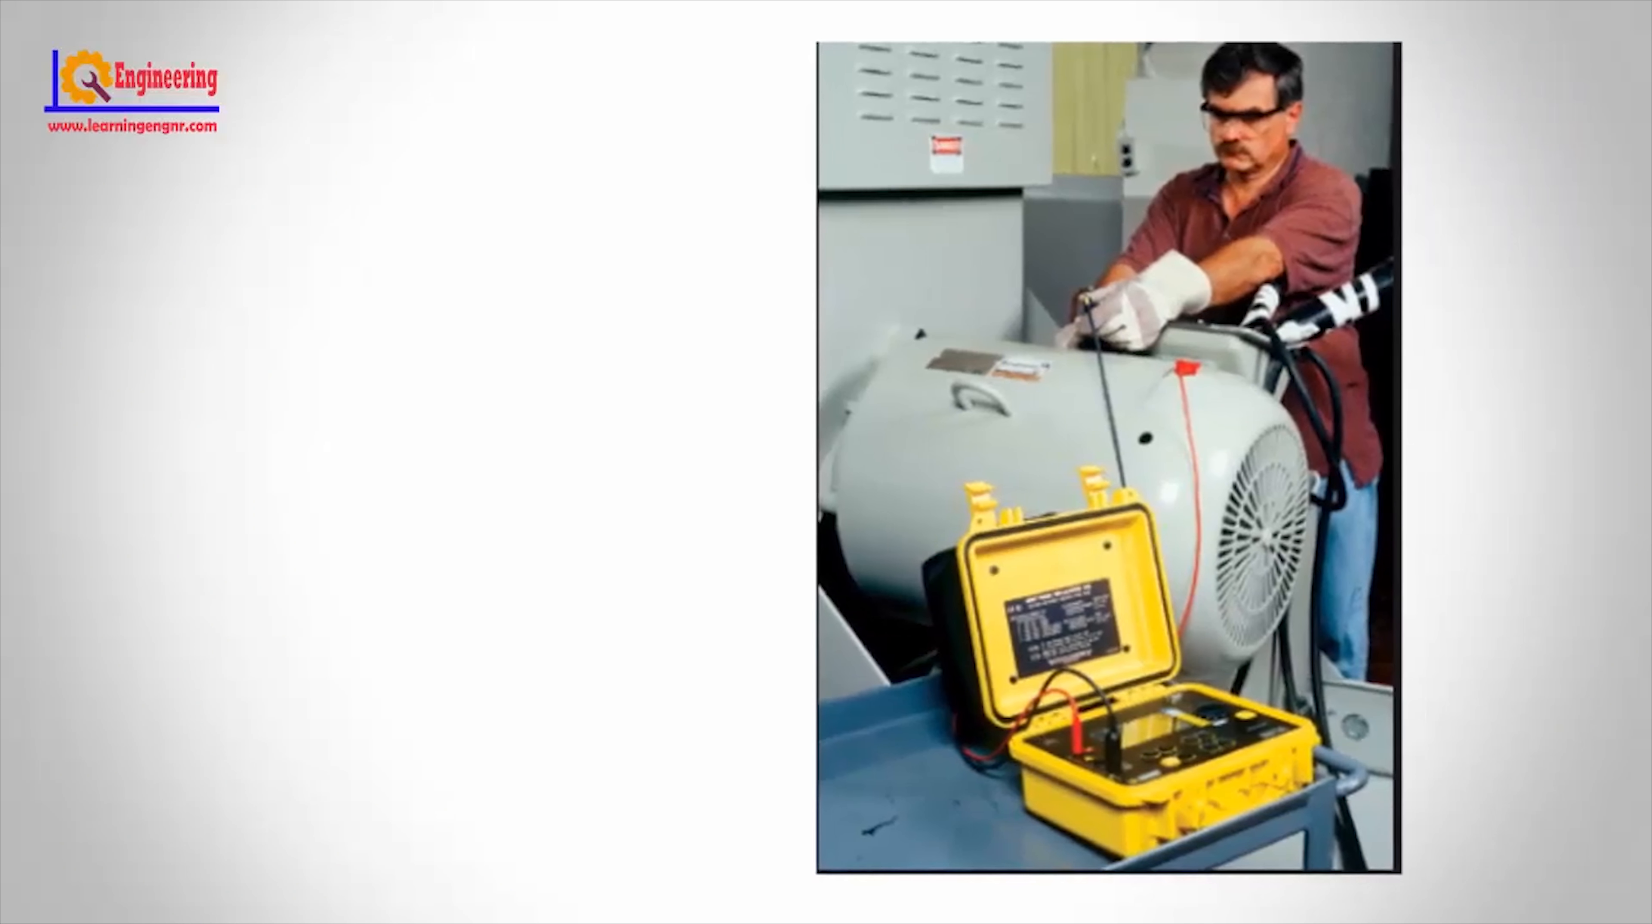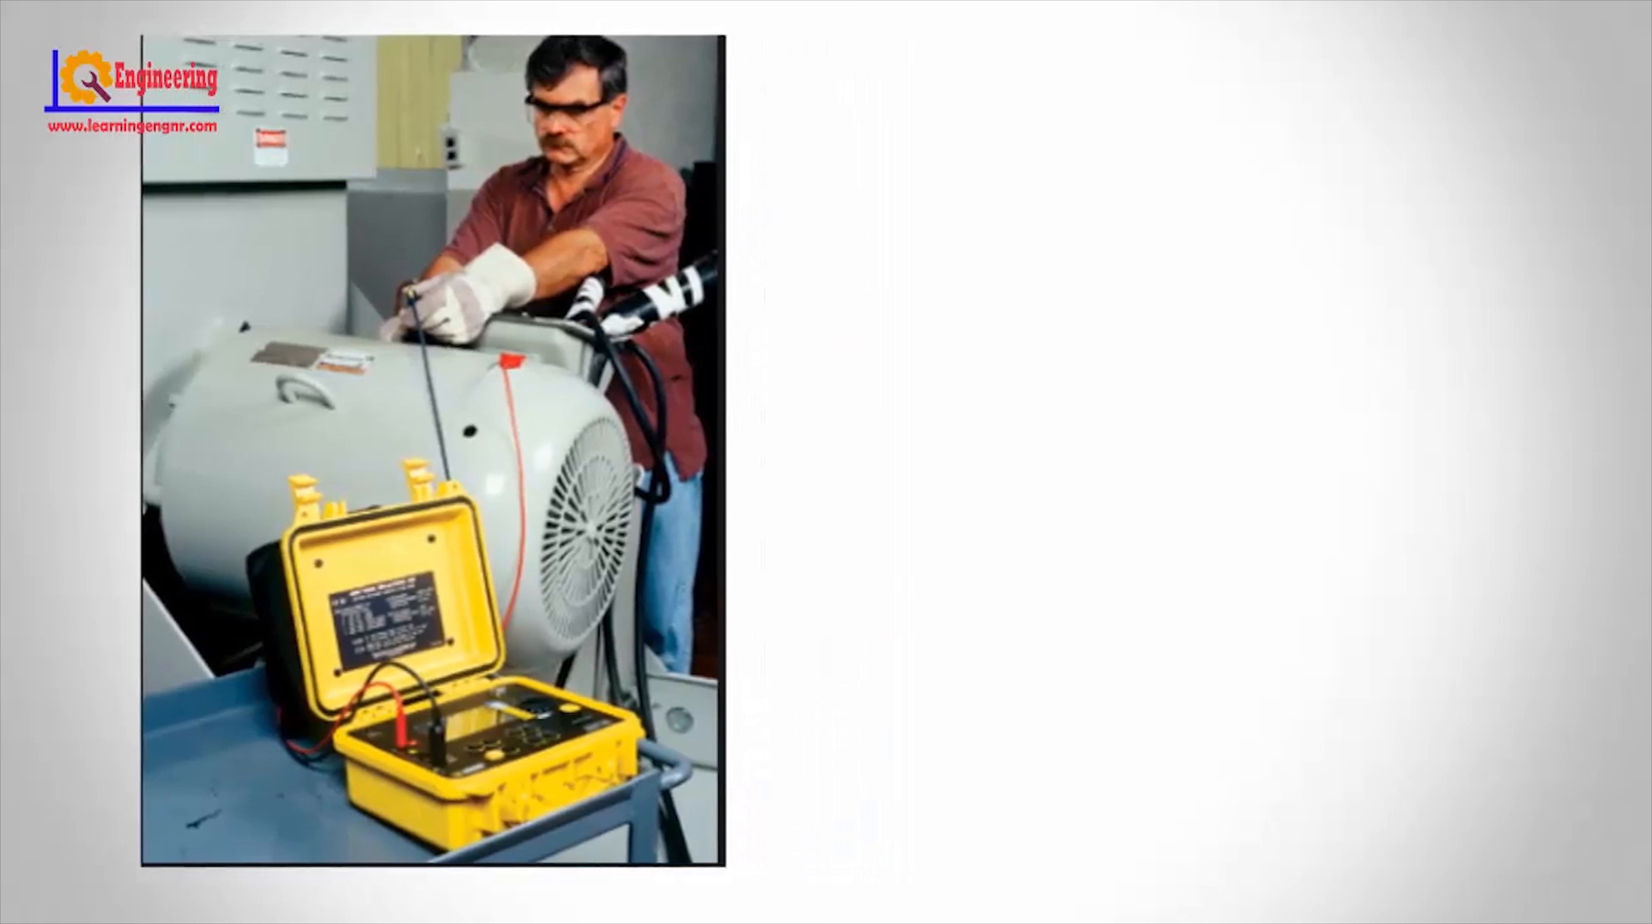The minimum acceptable value of resistance for a product to pass an insulation resistance test is 1 mega ohm. The insulation resistance test is not a substitute for the high voltage test. Many standards and safety agencies have specified this is a universal test for all products.